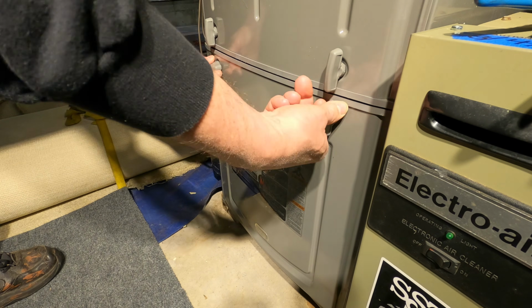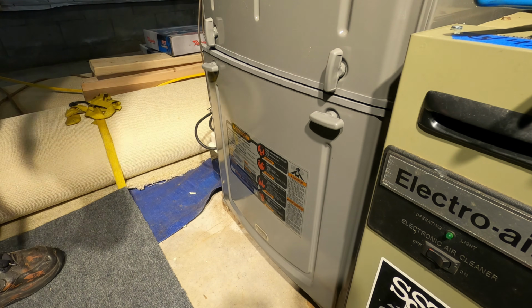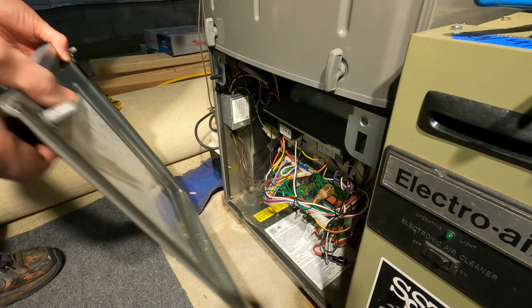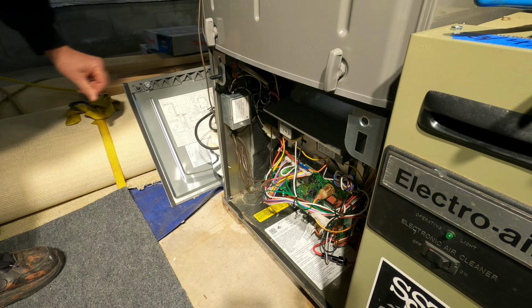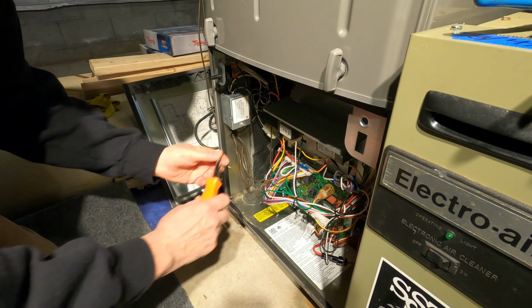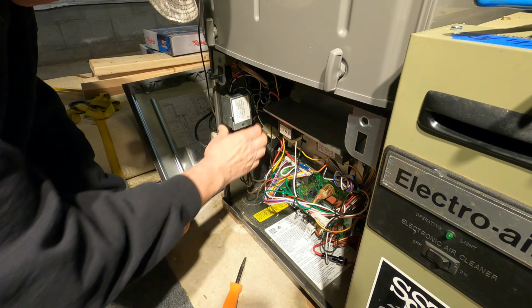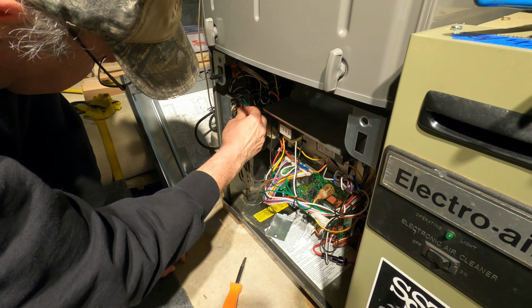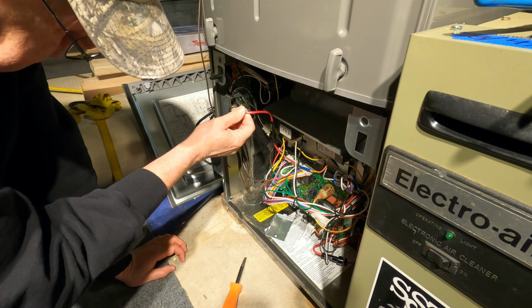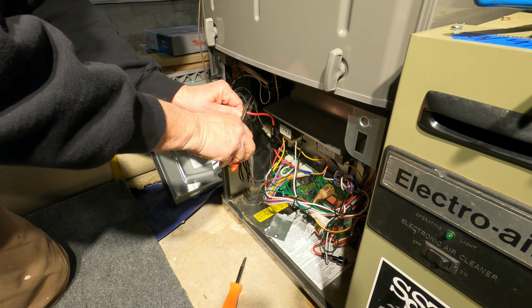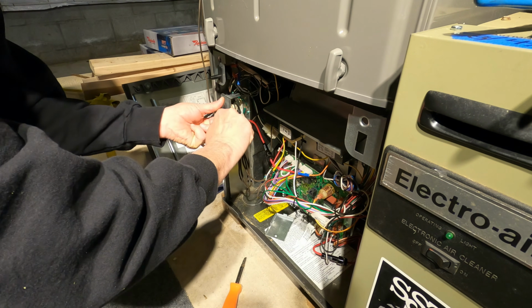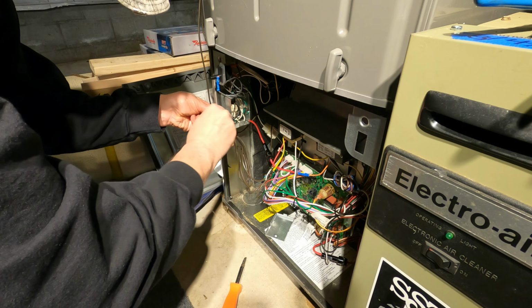Another commenter pointed out that the power into the furnace should be controlled by the safety switch on the furnace access panel, which isn't a bad point. I mean, the risk here is minimal because the relay also automatically turns power off, but it's common sense to have all the power in the furnace switch off when the access panel is removed. So I rewired the relay to get its power through that furnace safety switch. The furnace access panel safety switch is rated for 16 amps at 125 volts AC. Notice it also has a motor horsepower rating.